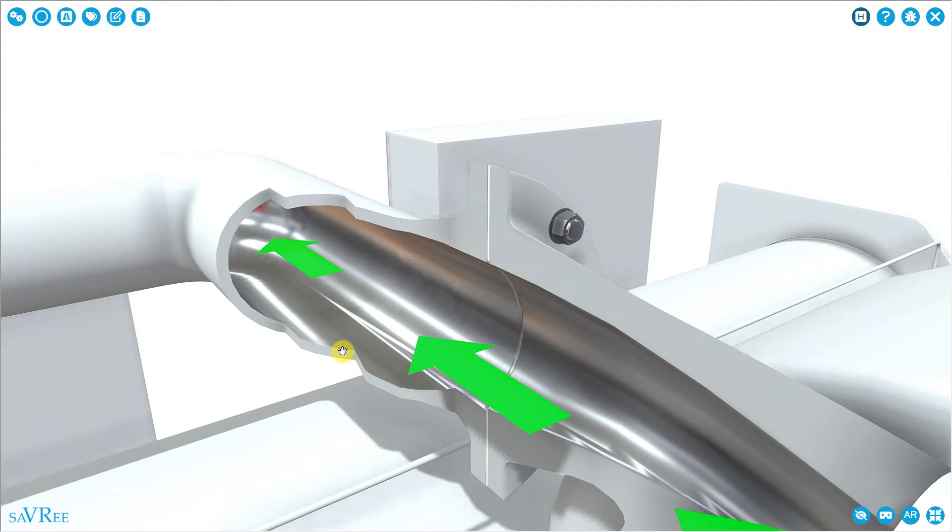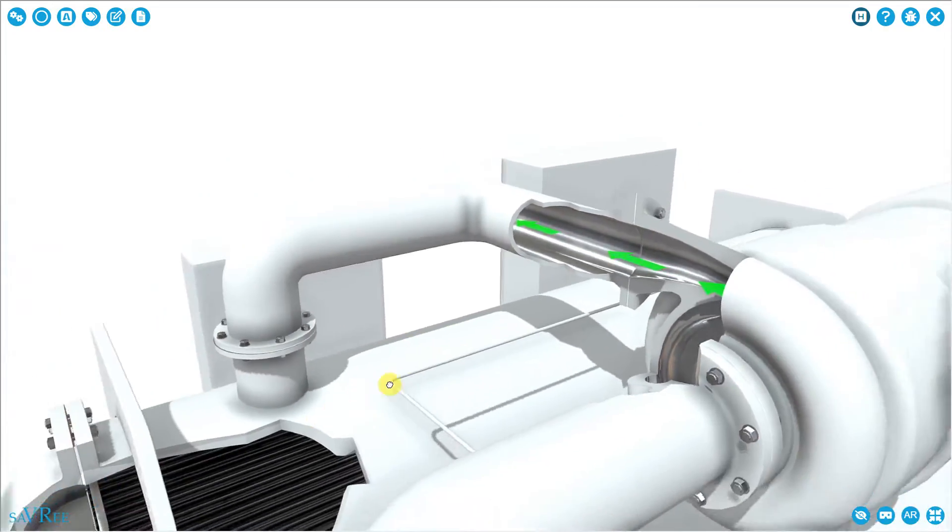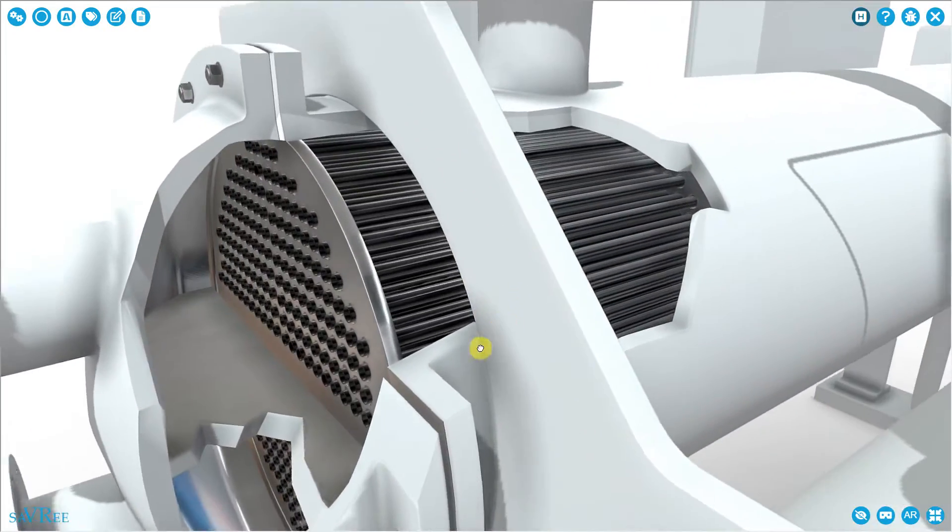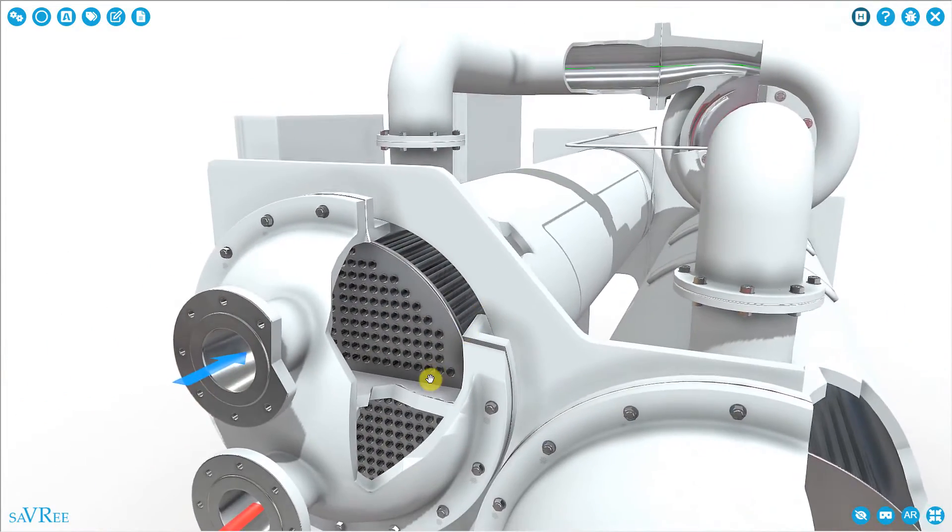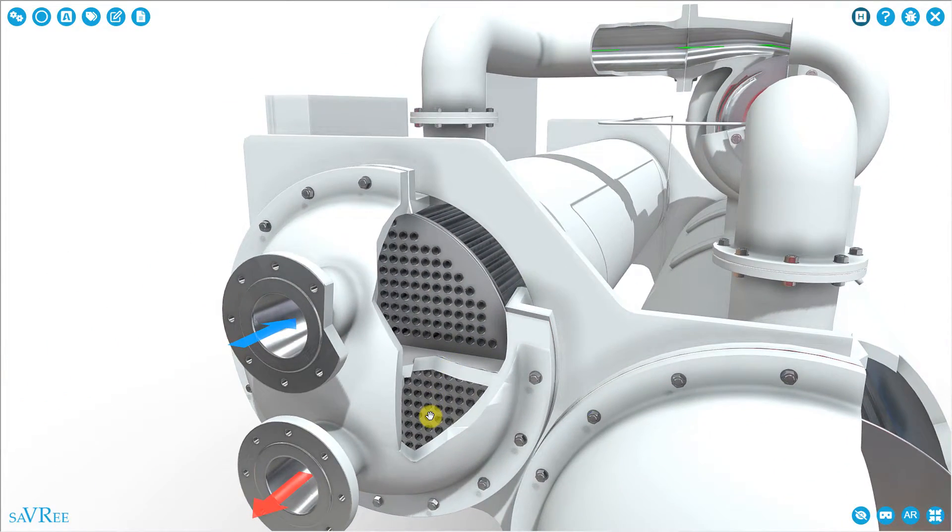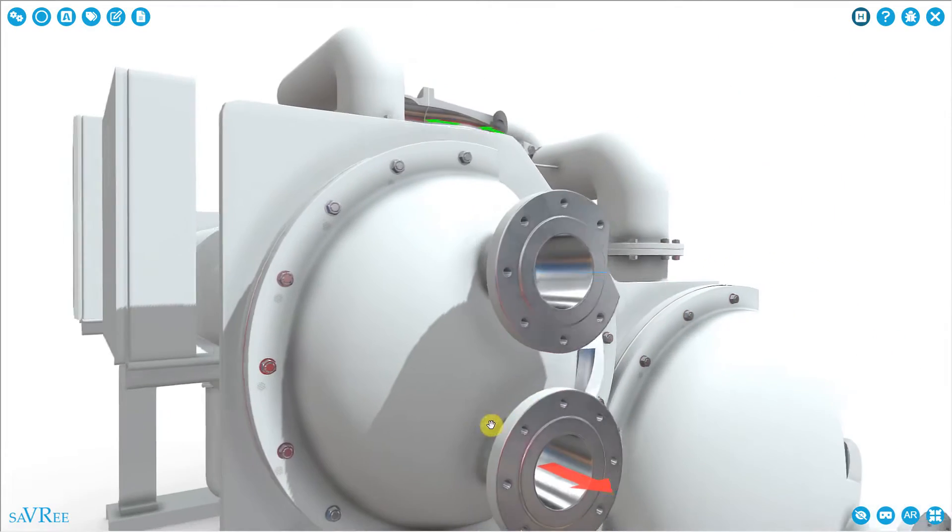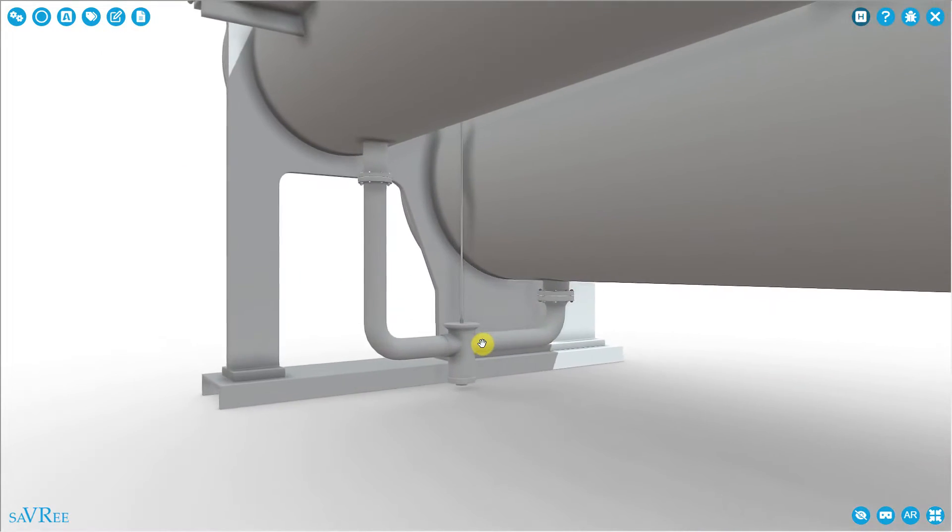We discharge the refrigerant from the compressor. It goes into a shell and tube heat exchanger. And this shell and tube heat exchanger forms our condenser because we condense the refrigerant from a vapor and turn it into a liquid. From there, the liquid refrigerant comes out.